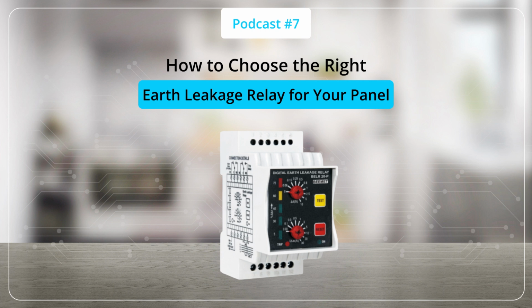Next comes the CBCT connection. The secondary wires from the CBCT are connected to the T1 and T2 terminals of the relay. An important installation rule is that only the phase and neutral conductors should pass through the CBCT window.